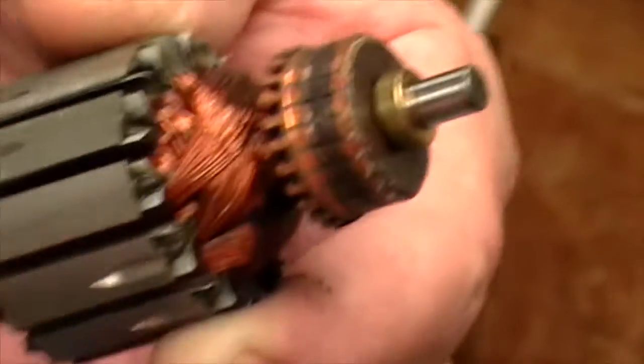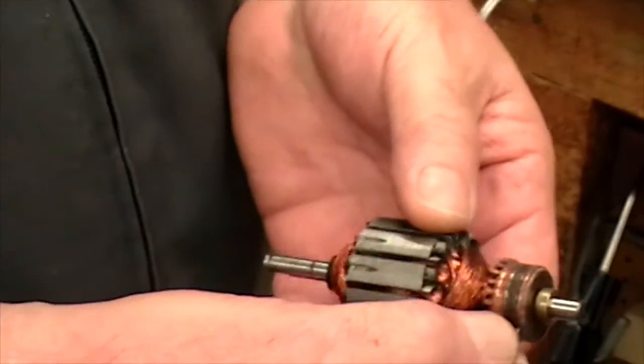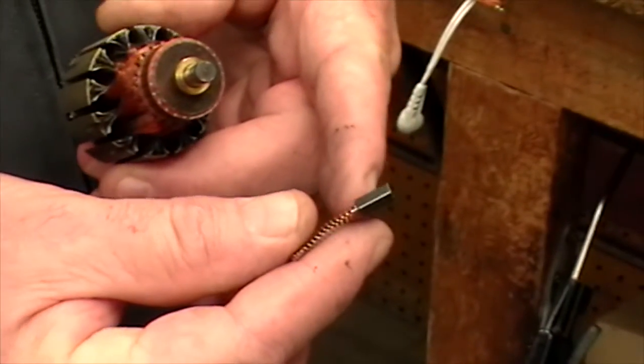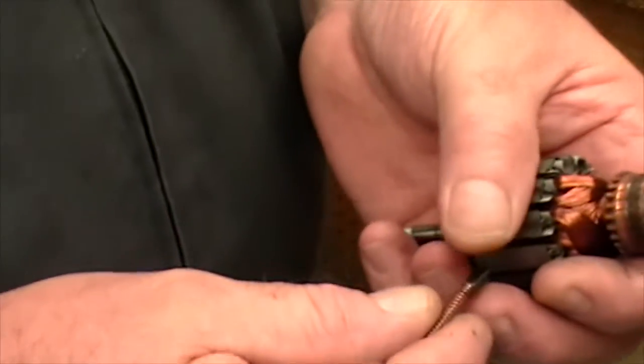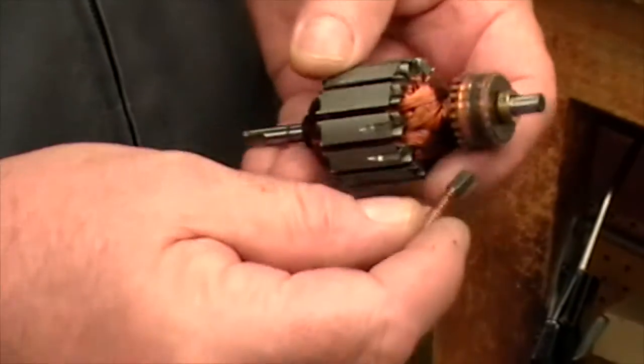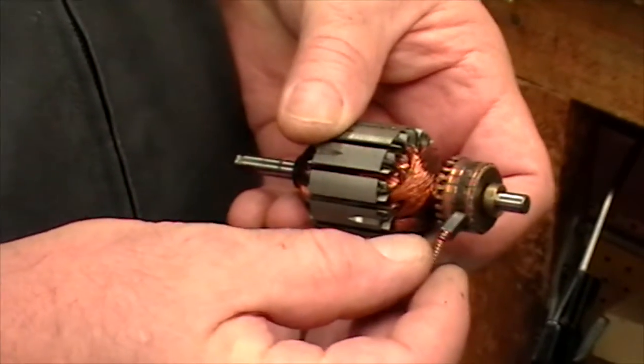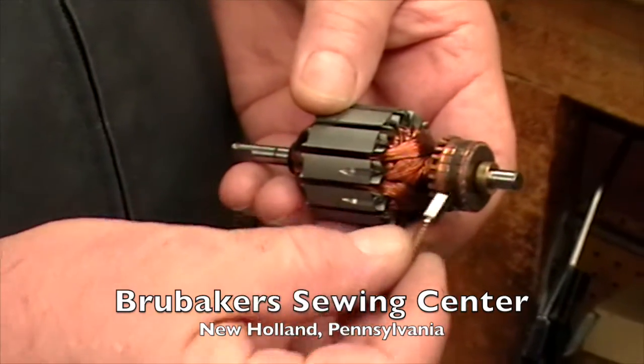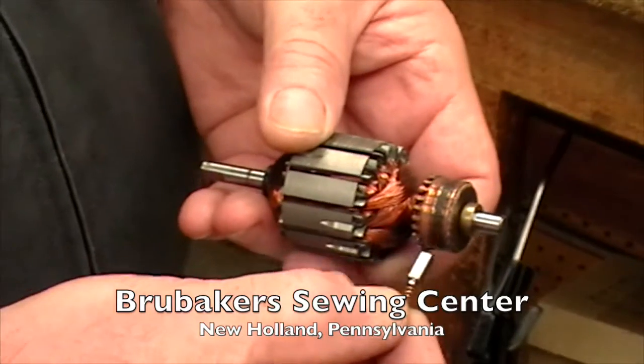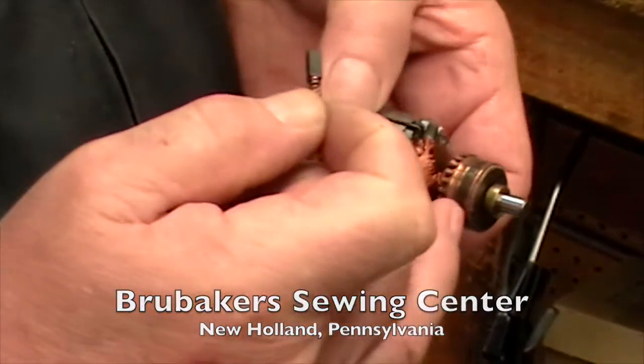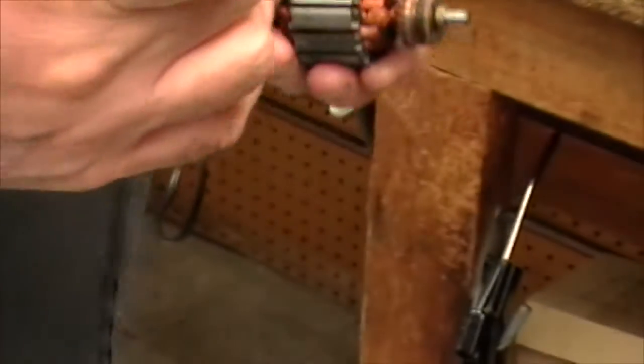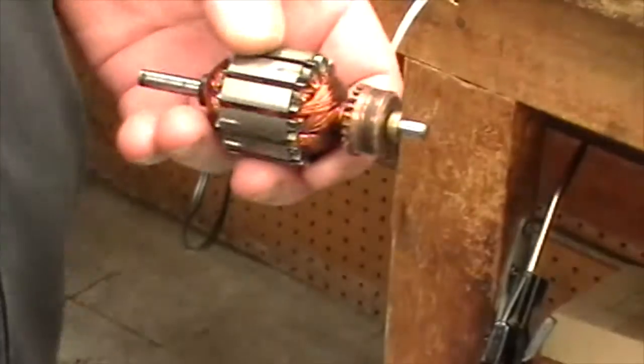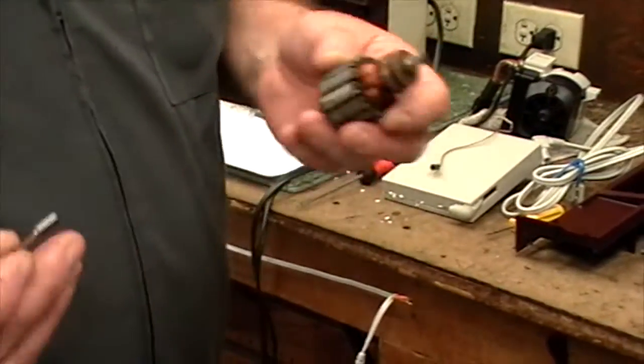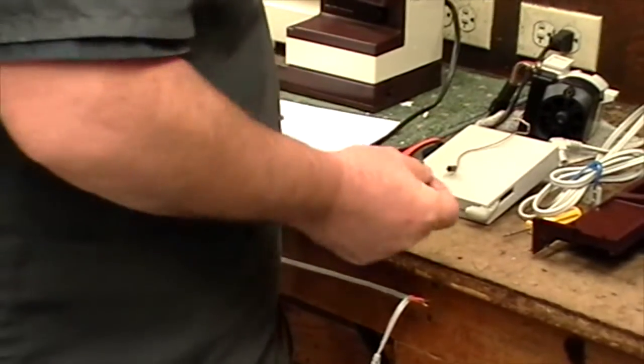When this brush wears down, this black part here will wear down. It'll wear like lead in a lead pencil. This is turning and this is rubbing on this. And after a while, this keeps continuing to wear down. Eventually, the only thing left is this spring. Now, this spring, being copper, still makes a contact. And what that does is allow this motor to still run with no brush, but rubbing the metal spring against the commutator. That'll start to cut a groove in this material here. Now you're going to get arcing, and you'll get an ozone smell. So that means you need work here, in this part and in the brush.